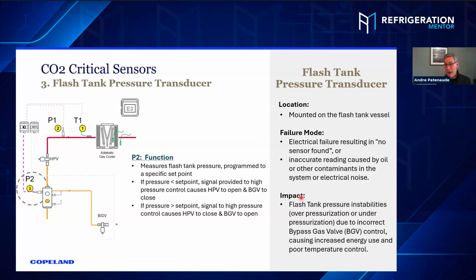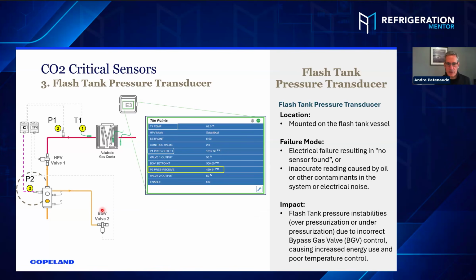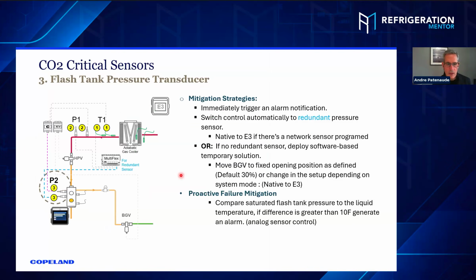So really, the impact of that sensor failing is flash tank pressure instability, overpressurization or underpressurization due to incorrect bypass. So that's a big one. And again, in E3, you can view exactly what that pressure transducer is doing and where the bypass valve is sitting, in this case, 52%. So what kind of mitigation strategies? Again, the same as the other two, right? Set an alarm.